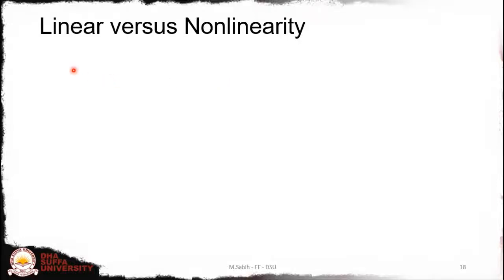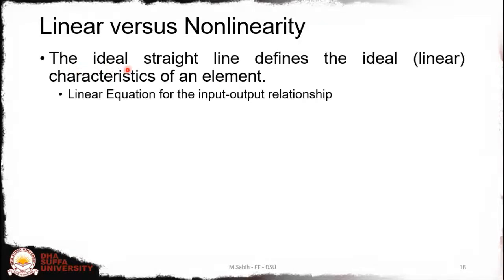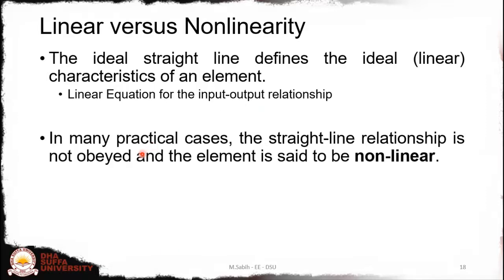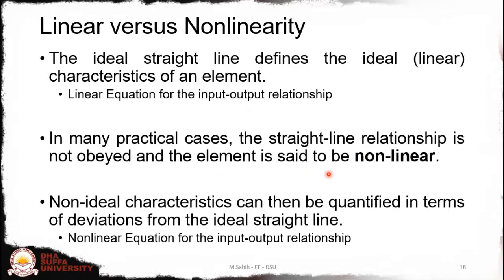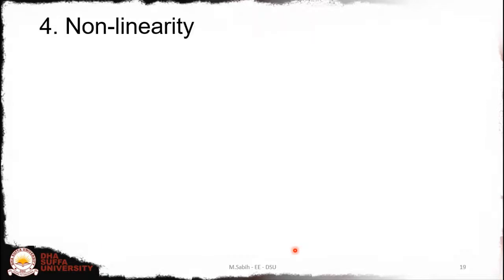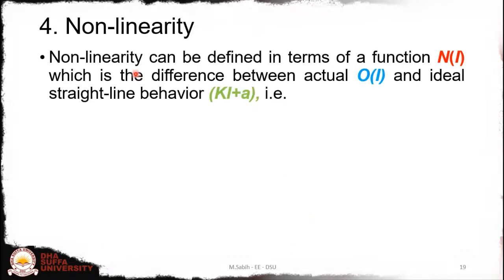In terms of linear versus nonlinearity, the ideal straight line defines the ideal linear characteristics of an element. The linear equation describes the input-output relationship, but in many practical cases this straight-line relationship is not obeyed and the element is said to be nonlinear. Nonlinear characteristics can then be quantified in terms of deviations from the ideal straight line. The nonlinearity is defined in terms of the function n(i), which is the difference between actual output and the ideal straight line.